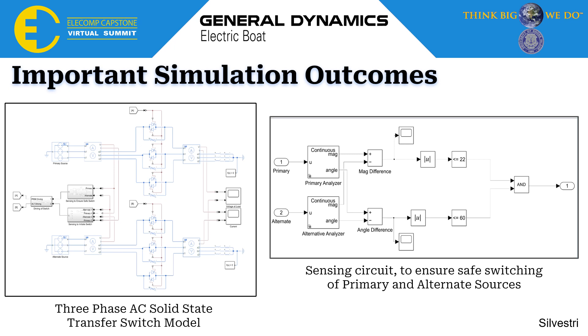So the waveform you see here is actually the voltage being monitored at the load of the transfer switch on the previous slide. In the left image, you can see the primary voltage source begins to experience a bit of a voltage sag, and at about 0.4 seconds the transfer switch initiates. On the right, with a much more zoomed in view, you can see that at 0.4 seconds the primary source gets driven to 0 while the secondary source is turned on with an extremely fast switching time of around 100 microseconds.